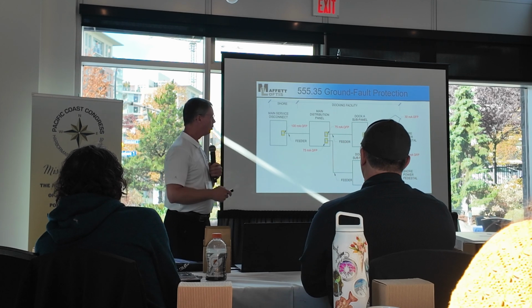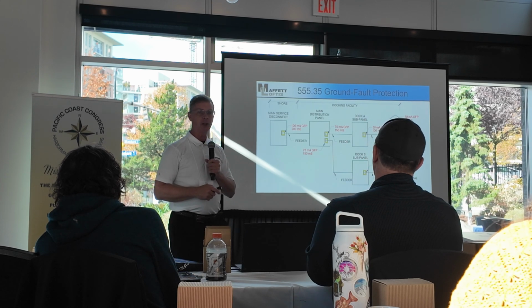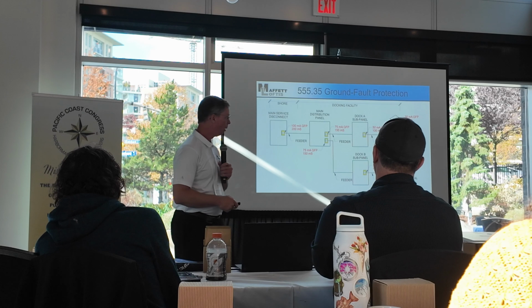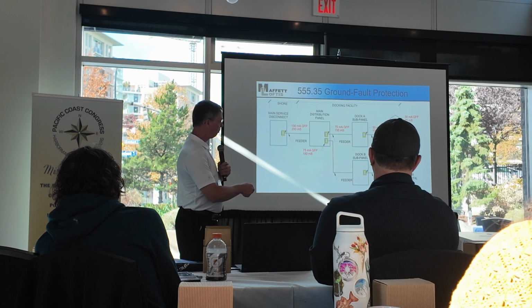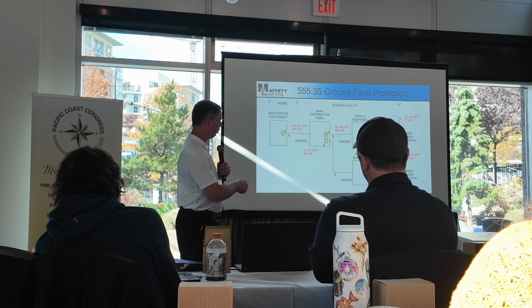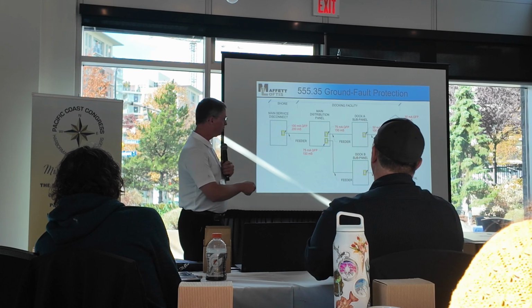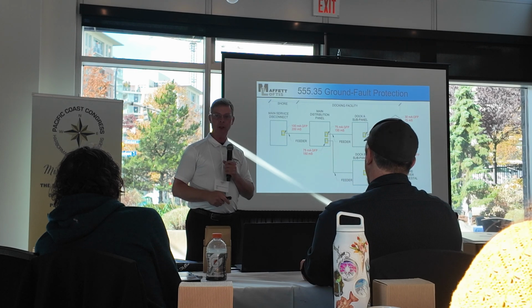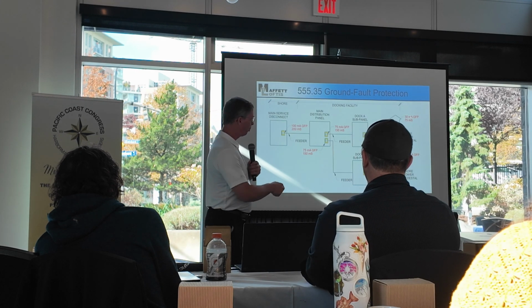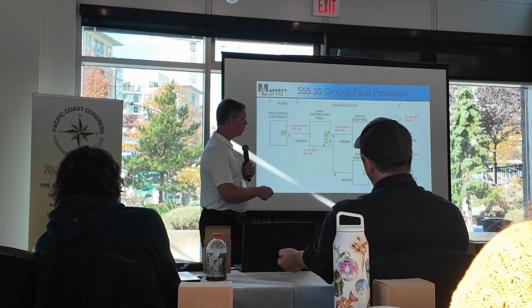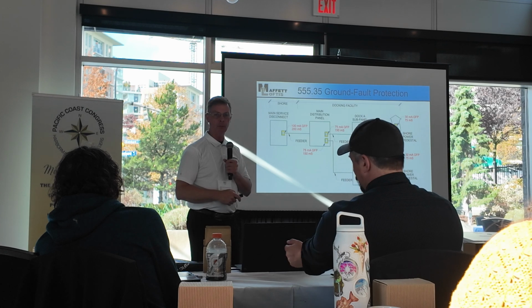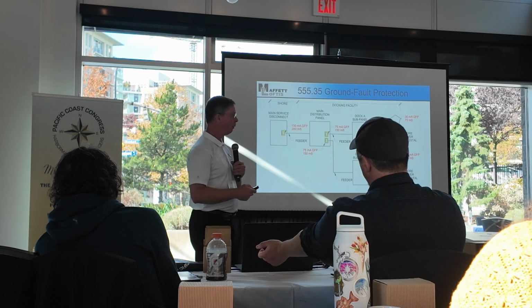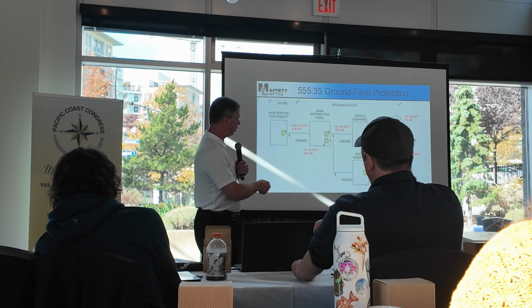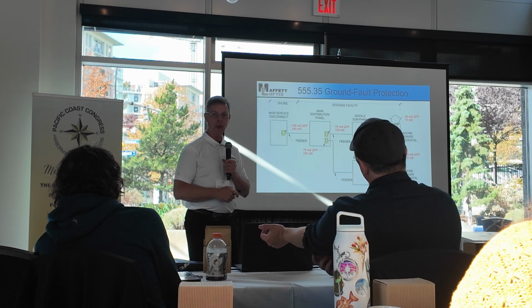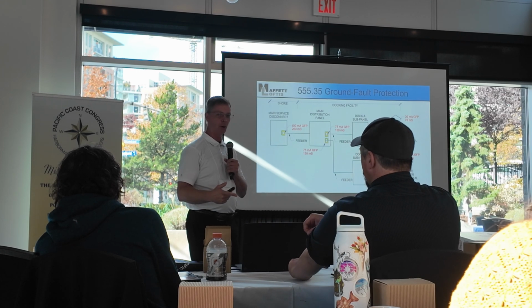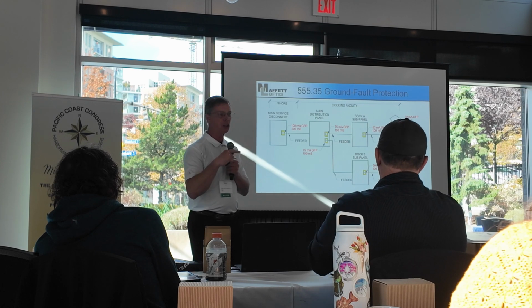We don't want that. Okay? What if we do this? Say that we can set the timings of when the GFPE systems trip. And so now, this is set at 75 milliseconds. That's at 100 milliseconds, 150, and 200 milliseconds. Now, say a boat comes in, plugs into there, and pulls 400 milliamps of leakage current. What's going to trip? It's the one with the lowest and the quickest. Because this will clear the fault and stop the leakage current at 75 milliseconds. And so this right here is set at 100, so this right here will never see that leakage current long enough to trip that upstream GFPE device. So now this is fully coordinated.